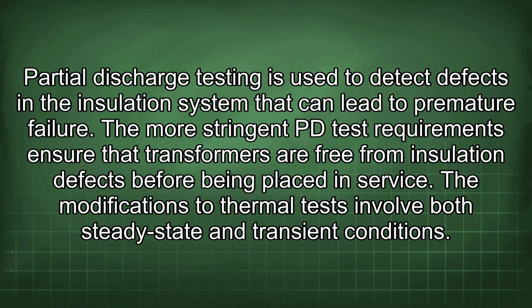Partial discharge testing is used to detect defects in the insulation system that can lead to premature failure. The more stringent PD test requirements ensure that transformers are free from insulation defects before being placed in service.